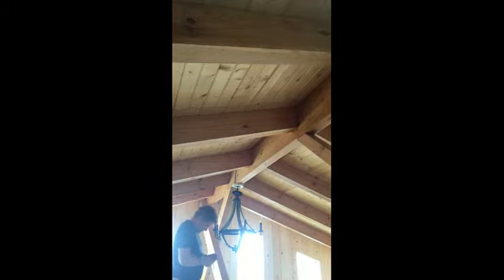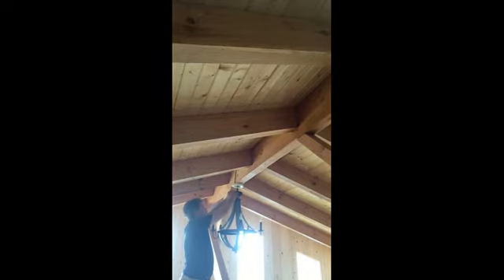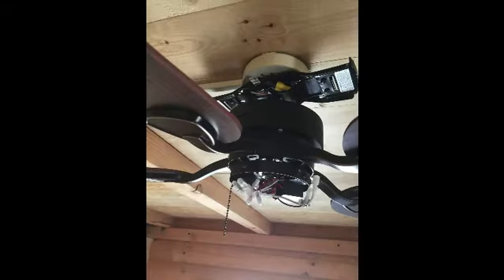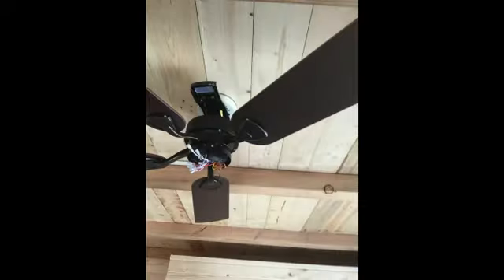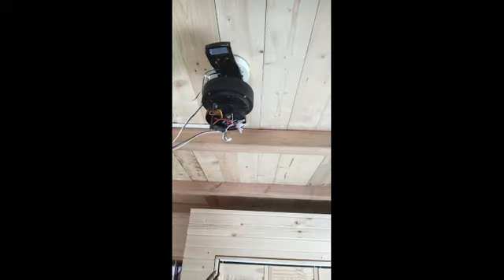So once the room is done, right? Remember you ran one feed from the panel box off of one breaker. The next room has to be done. That's going to be another breaker, and then the next room and the next room. And again, make sure your electrician is aware of what's going on. If you have huge rooms, like a great room, and you may have a bar, a jacuzzi and things, you may have three to five different circuit breakers going on, so you need to understand the loads of these breakers. Remember that a 20 amp breaker is for 12 gauge wire, and a 15 amp breaker is for 14 gauge.